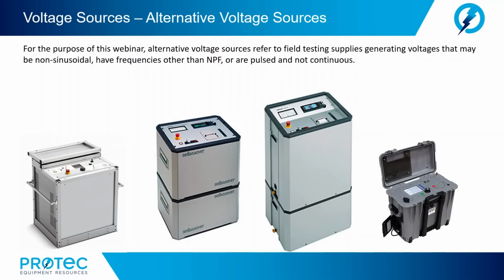All right, we talked about direct current. We talked about alternating current at 50, 60 Hertz. We talked about AC current at near power frequency levels. So now let's talk about alternative voltage sources. For the purpose of this webinar, alternative voltage sources refer to field testing supplies generating voltages that may be non-sinusoidal, have frequencies other than near power frequency, or are pulsed and not continuous.